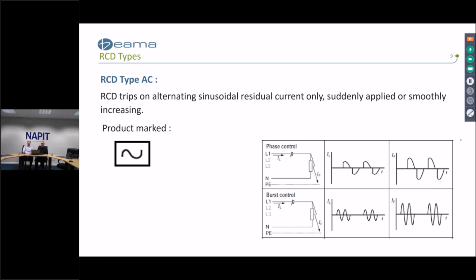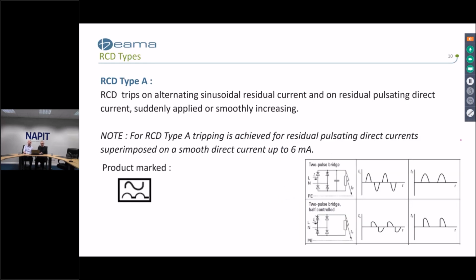So a Type AC device is suitable for these kinds of waveforms as well, but it must be positive and negative so that you get an overall RMS value. The products are marked so that you can identify them, and for the Type AC, it is a sine wave in a box, and that will be marked on the front of the RCD. So that's a means of identification.